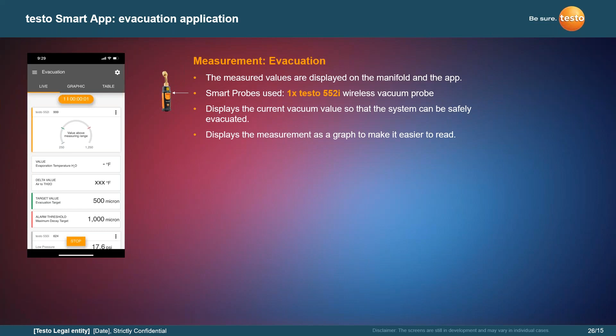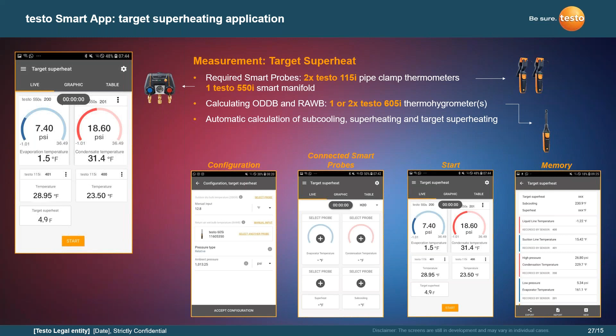Again, target superheat, nothing changes here. We're looking at the same readings. We're going to need a dry bulb temperature and a wet bulb temperature inside. So your outdoor dry bulb and your return air wet bulb is really what you want, with the return air wet bulb as close to the coil as you can get. I failed to mention that before, but that's how you want to do that.